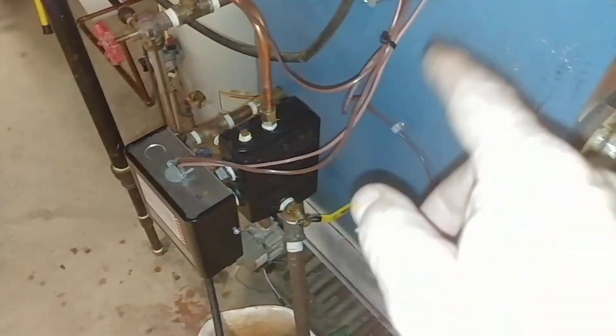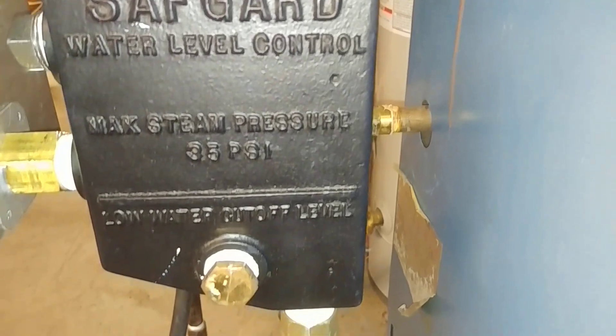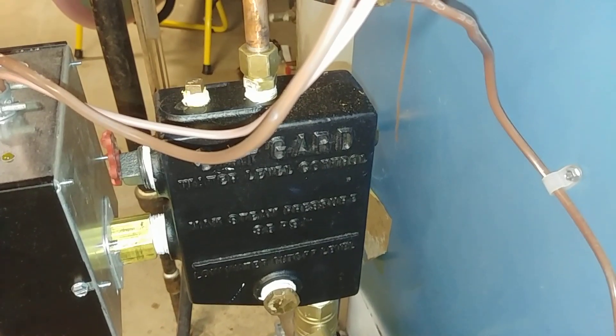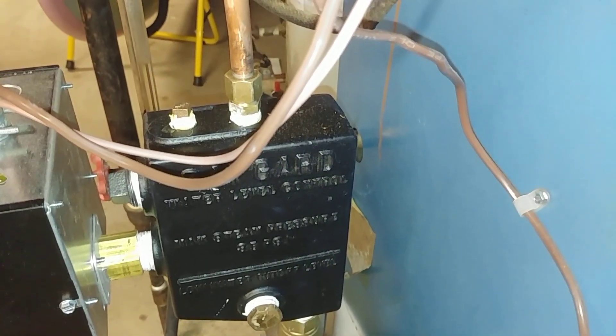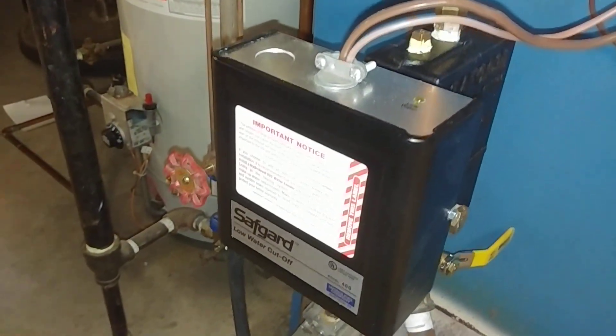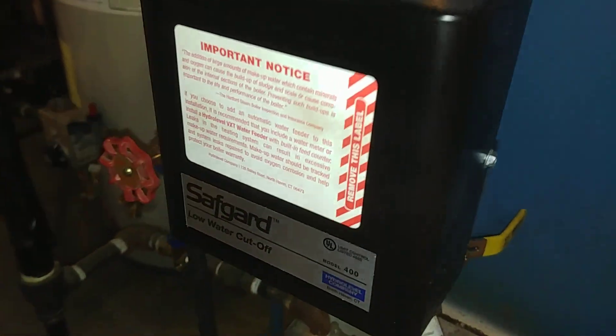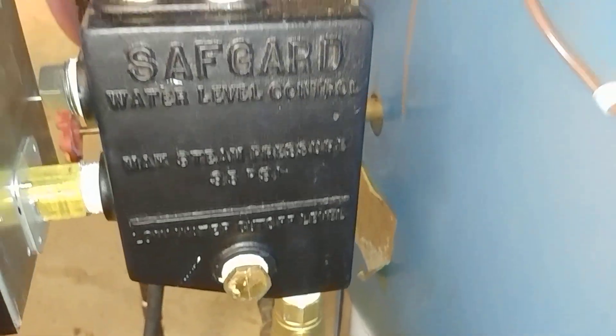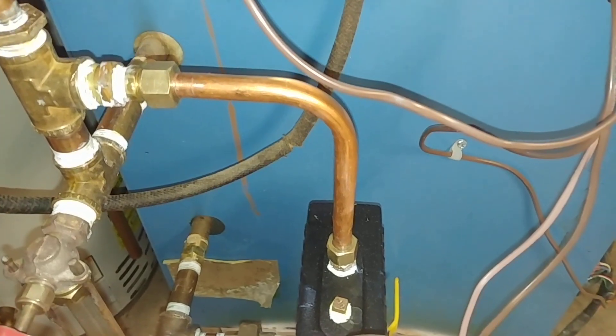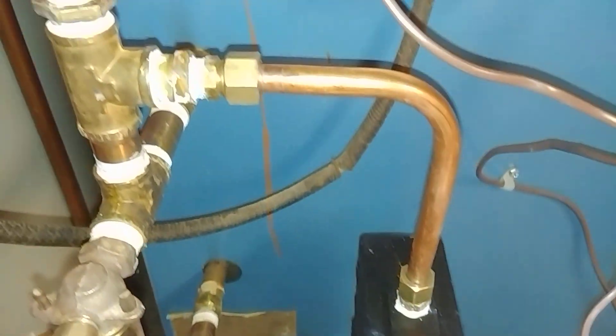The way that's generally done — if there's not a tapping on these older boilers — you can get this manifold, model number 711C, and mount an electronic low water cutoff on it. We've got a Model 400 Safeguard, and you add it very similar to a 67 with the soft copper line.